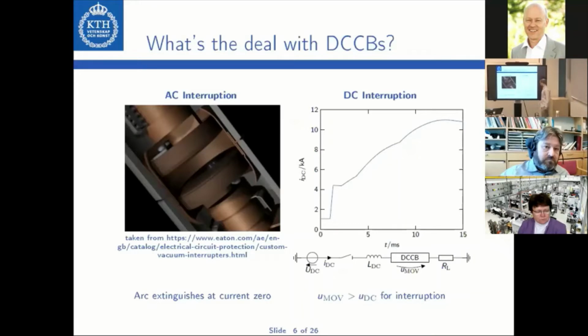But anyway, maybe I would just repeat this. So this simple DC circuit has a DC source and a DC circuit breaker. And the DC circuit breaker has to insert a counter voltage that exceeds the DC source voltage in order to interrupt the current flow. Two practical implementations are possible. One would be a typical AC circuit breaker that has an arc voltage that is so high such that it exceeds the DC source voltage. This is, however, not feasible for HVDC applications.